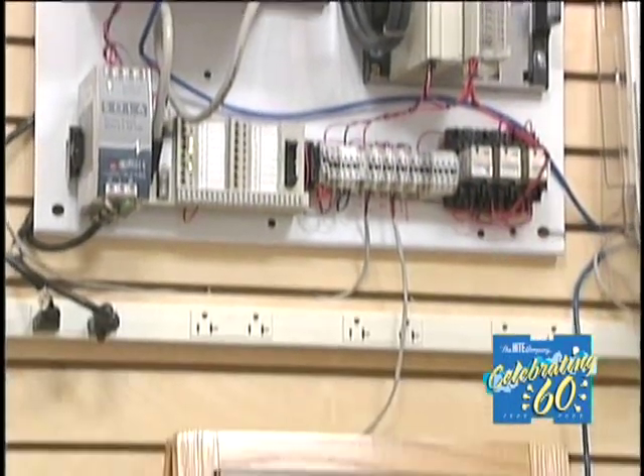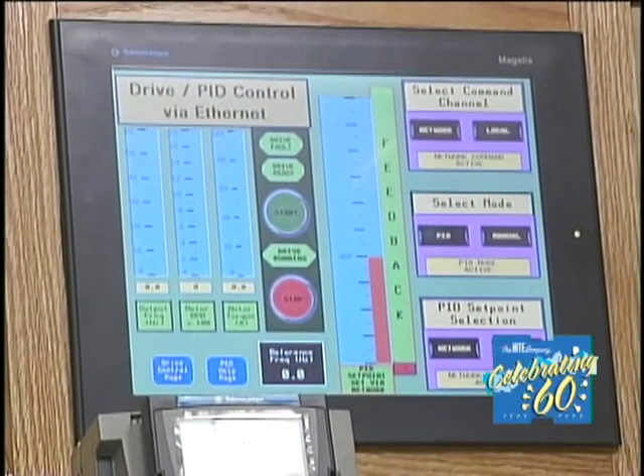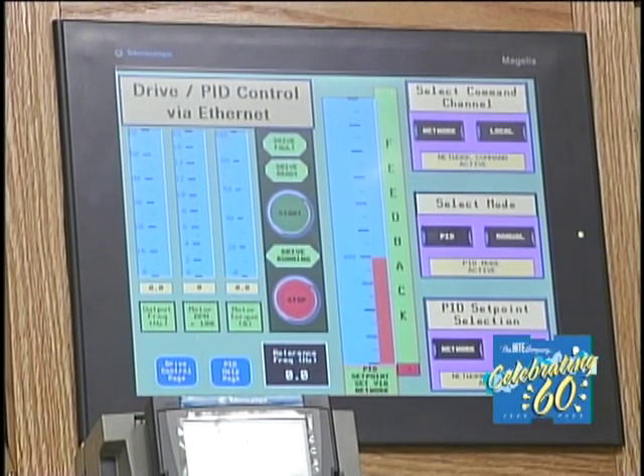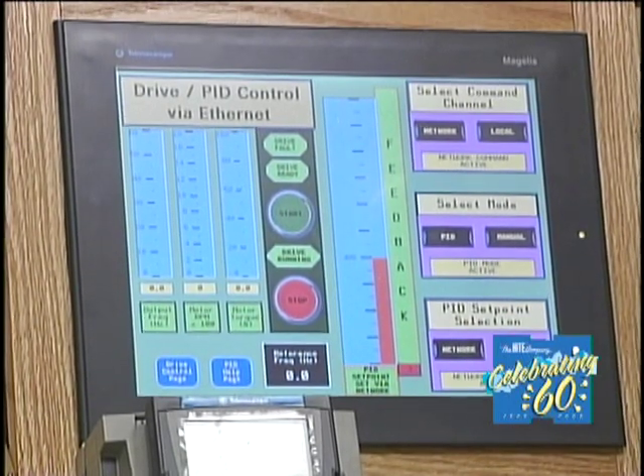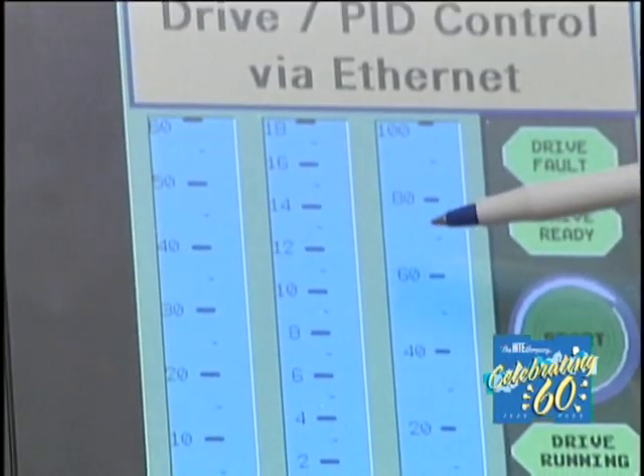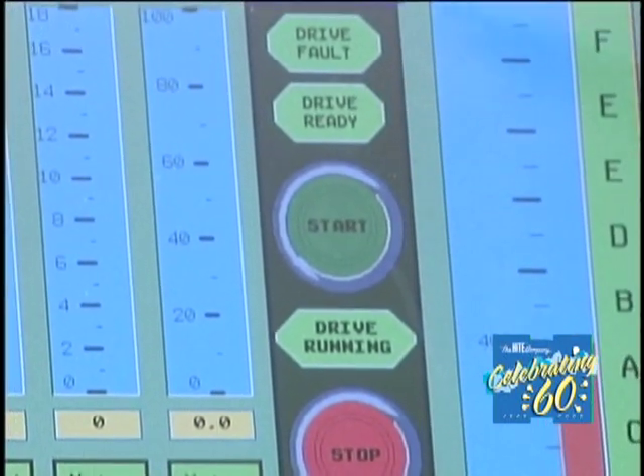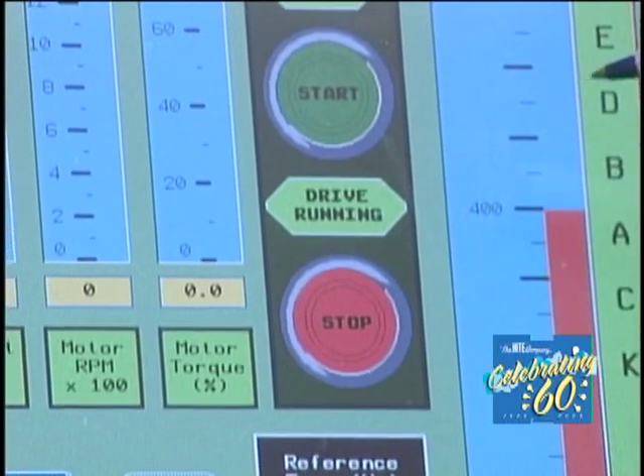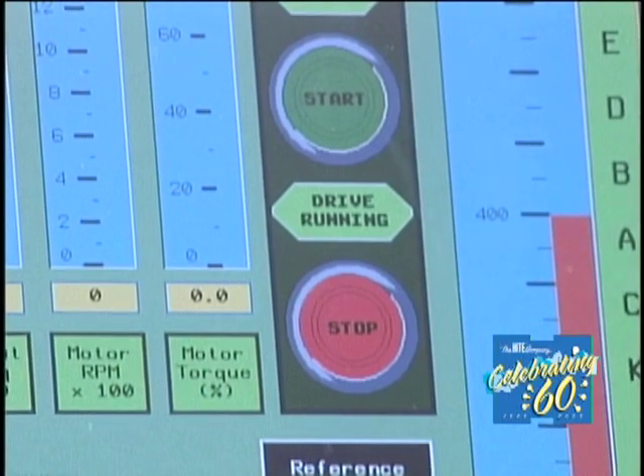We have a Modicon Magelis HMI communicating over Ethernet to the PLC. This is where we're giving most of the commands to the drive and doing the monitoring. On the screen we can look at the output frequency, the motor speed, and get an indication of motor torque. We have start/stop push buttons to start and stop the drive, and annunciators for drive ready, fault, and running status.